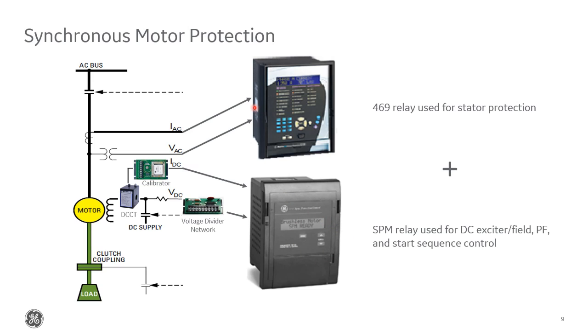The 469 would have the usual line current and voltage connections going to it, and then the SPM would receive signals from the field. A DC CT would provide the current signal. In the case of the SPM, we had a calibration module in between to process the signals. And the voltages across the field windings and also at the exciter itself would be brought to the relay by way of this voltage divider network, which just steps down the signals for relay processing.